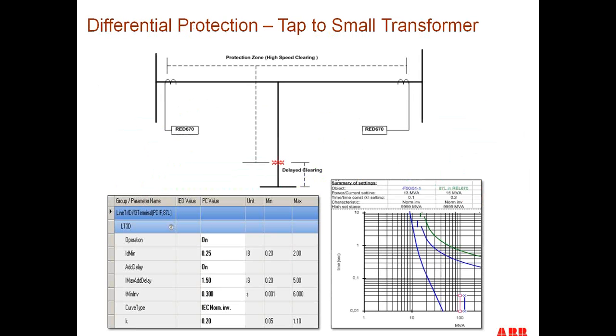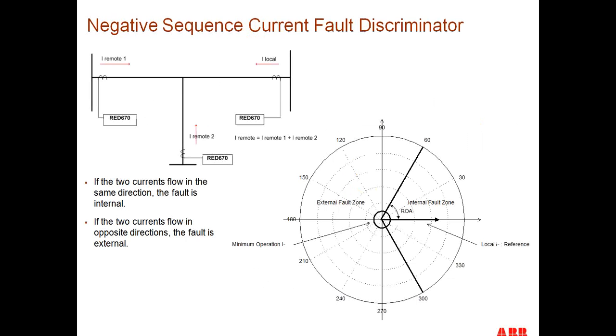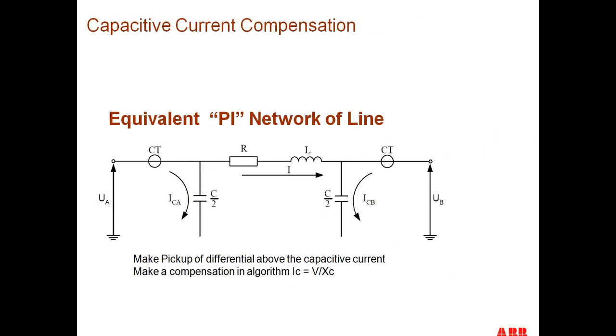Okay, now that we covered the resistance fault, the next thing we need to worry about is capacitive current compensation. What that means is that if we have a transmission line, we're going to have a certain amount of capacitance on the transmission line. The charge current on the transmission line looks like a through fault or an internal fault, because it's current that's going into the line and not being seen at the remote terminal.